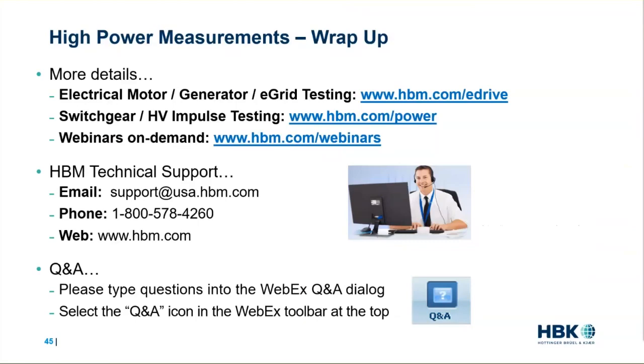You mentioned eGrid. Is it okay to sample slower than 2 million samples per second when measuring these signals? Yeah, actually, what we do for the HBM brand products, we actually offer a 200 kilosample per second sampling rate. Instead of the 2 million, you can sample, for example, up to 200 kilosamples per second on every channel for eGrid applications, which is very cost effective since electric grid signals, they're much lower in frequency than eDrive signals. They're typically at a fixed fundamental frequency of, let's say, 50, 60, or 400 hertz. So then the sample rates can be lower.